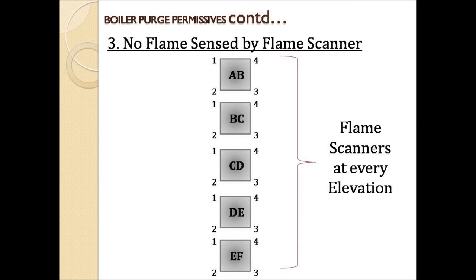The third boiler purge permissive is no flame should be sensed by a flame scanner. The picture in this slide shows the location of flame scanners situated at every corner and at every elevation of the boiler. This graphical representation is typically for a 270 megawatt plant or 890 TPH boiler. There may be more elevations for a 600 megawatt plant. If any one of these flame scanners senses flame in the boiler, then we will not get the permissive for boiler purging.